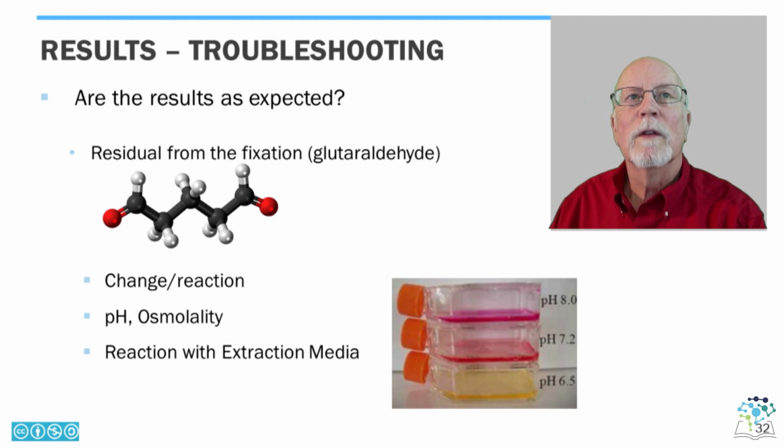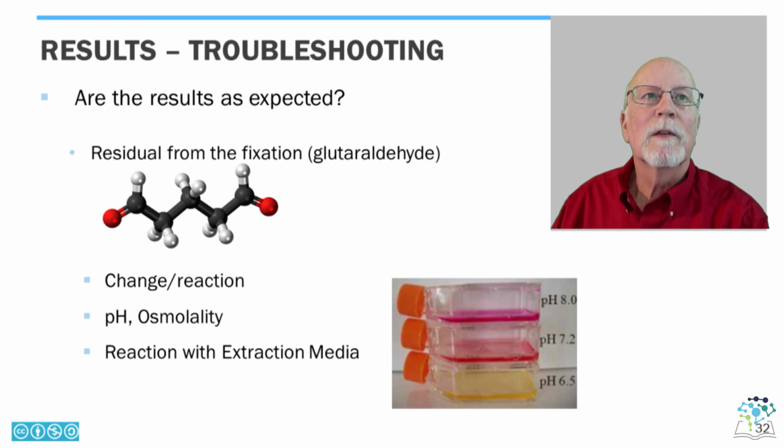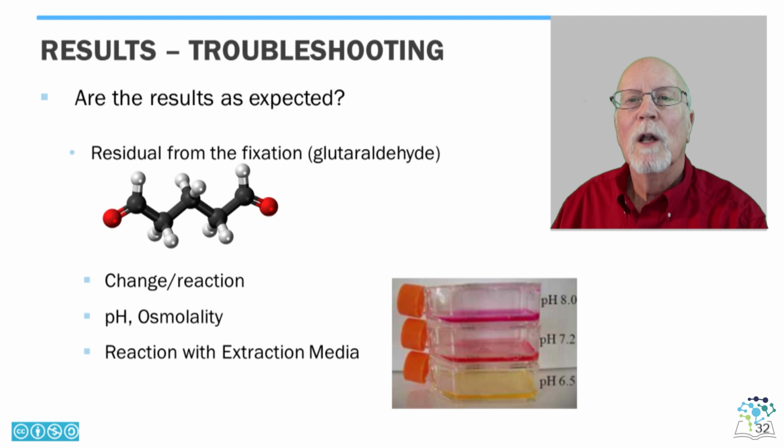The volume of the solvents used in the extraction is dependent upon the surface area of the device, and mistakes in calculation of surface area are a common source of improper extractions, which may also lead to repeated tests.